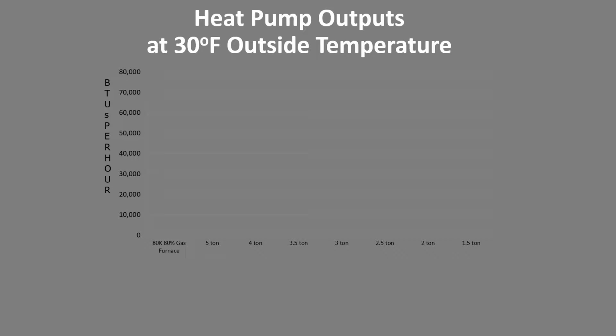Another way of looking at it, if you're going to use a 30-degree balance point, is what's the heat loss at 30 degrees? It turns out 30 degrees in Portland, Oregon is exactly the same temperature as 30 degrees in Bend, Oregon. So one thing you could do is go into your software program and say, I'm going to override the design temperature. I'm just going to call it 30 degrees. That way I'm going to go into the detailed capacity tables and just see what their output is at 30 degrees.